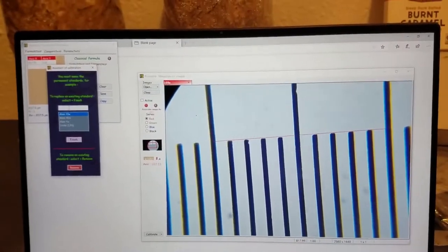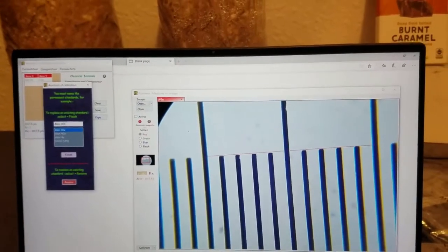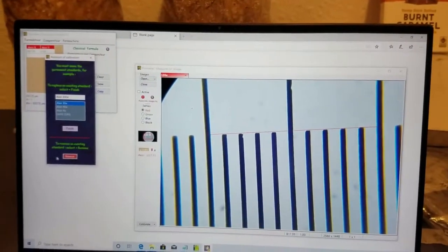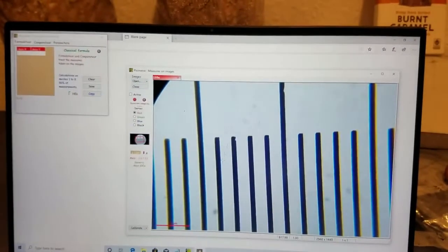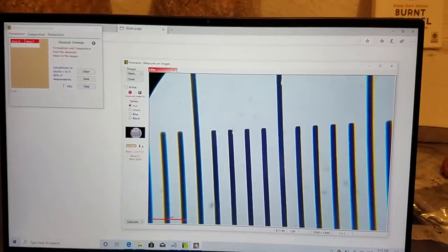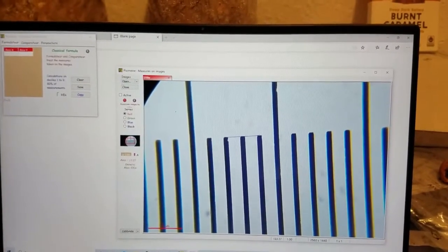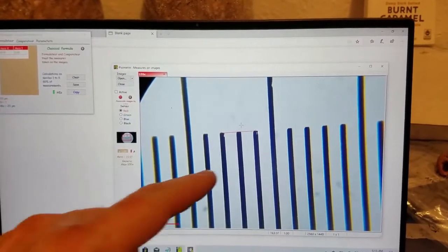And this is with the microscope, Alan microscope, and the objective 100x. And the standard is recorded. And just to test it, if we were to measure from here to here, it should measure 20. 19.97, super close.